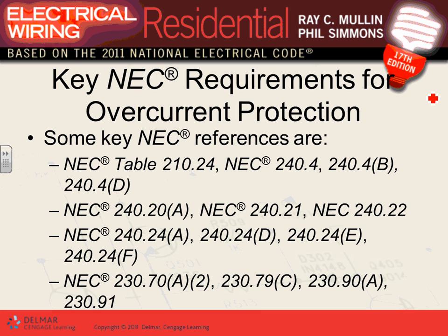There are several articles about overcurrent protection devices. Section 210.24 covers the maximum overcurrent protection device for branch circuits — like 15-amp and 20-amp circuits based on conductor size. Section 240.4 tells you to size your overcurrent protection device based on the ampacity of the conductor.